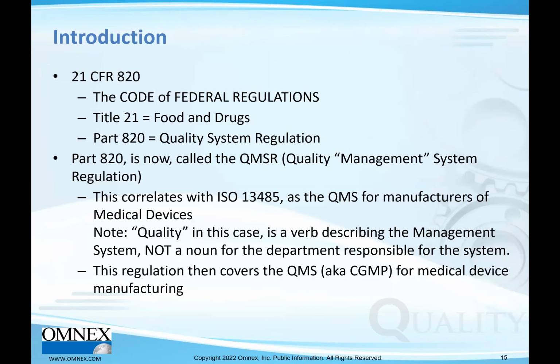An introduction to 21 CFR 820. What's CFR? CFR is the Code of Federal Regulations, often called the Federal Register. So if I mention the Federal Register, that's what we're talking about, the Code of Federal Regulations. Title 21 is the title of the Federal Register devoted entirely to food and drugs. Part 820 is the quality system regulation for the medical device QMS, quality management system. However, Part 820 is now being called the QMSR, quality management system regulation, instead of QSR. This correlates with ISO 13485 as the QMS for manufacturers of medical devices.